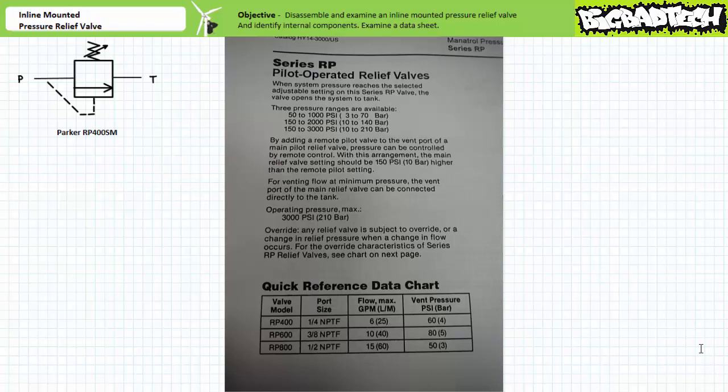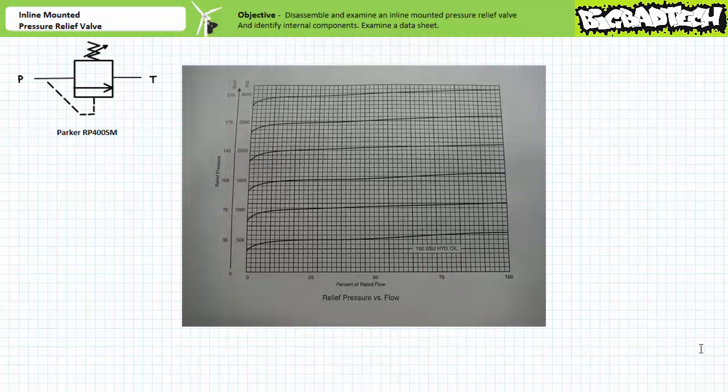The quick reference chart shows us that this particular valve is designed to accommodate a flow rate of up to 6 gallons per minute, or 25 liters per minute. Looking at the relief pressure versus flow rate graph on the next page, we observe a collection of curves characteristic of a pressure relief valve exhibiting pressure override. Pressure override is essentially a change in relief pressure as a function of flow rate. Note the curves all use the same reference condition, a hydraulic oil with a given viscosity or thickness in this case of 150 SSU. We'll discuss viscosity and viscosity units in later lectures.